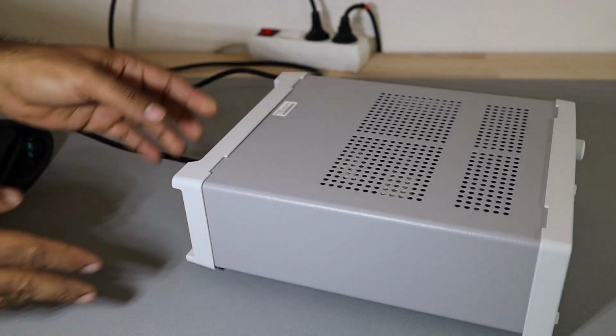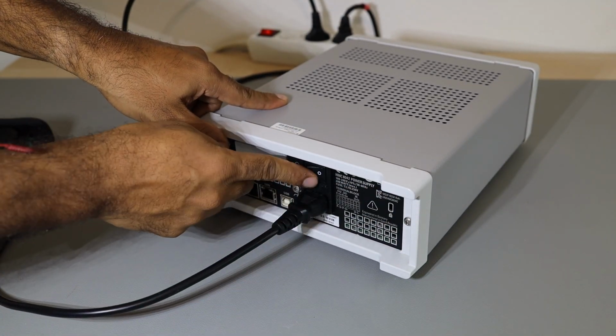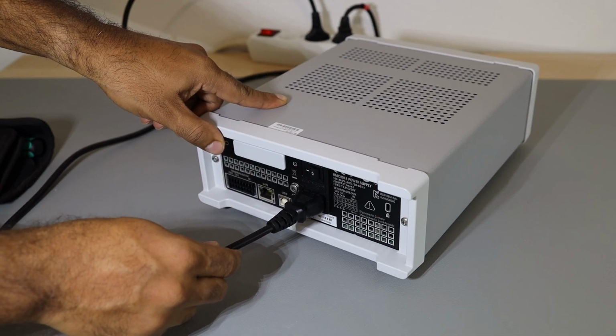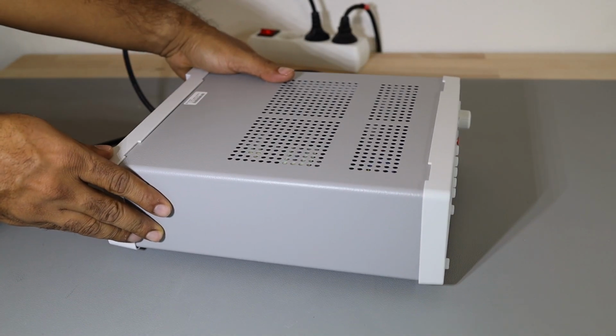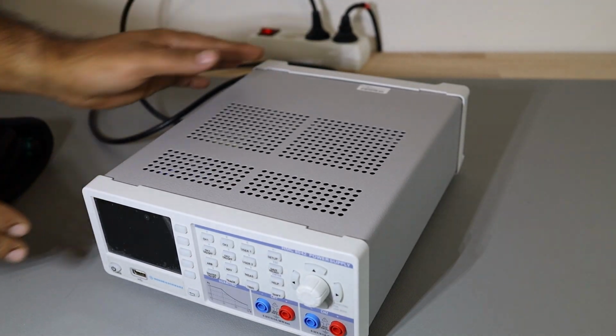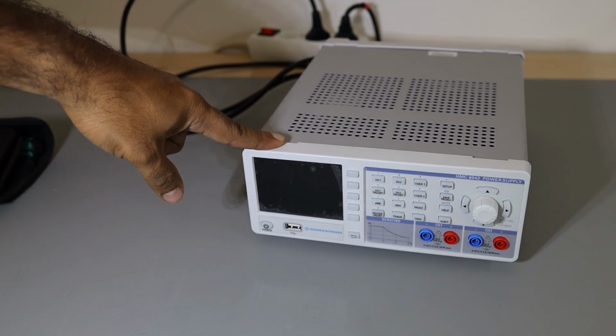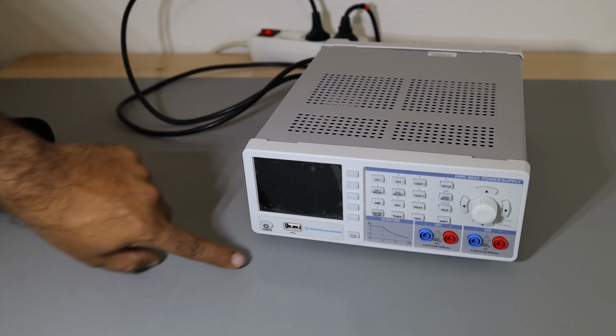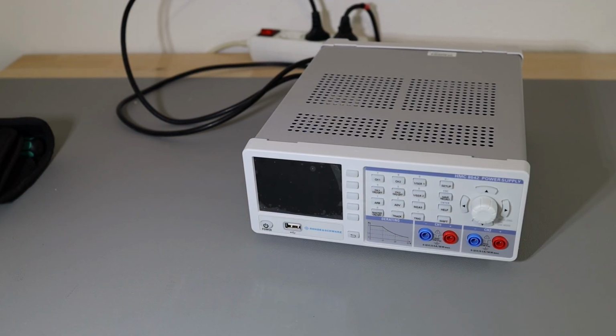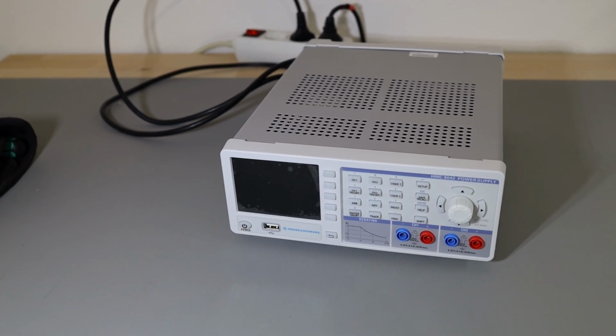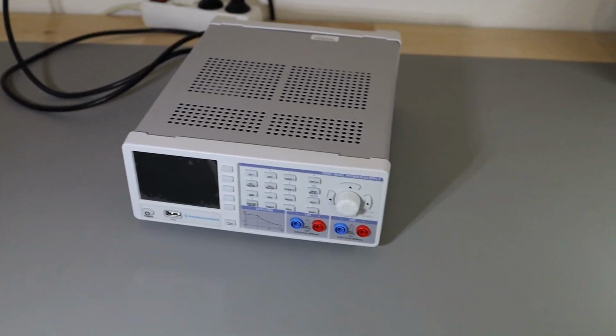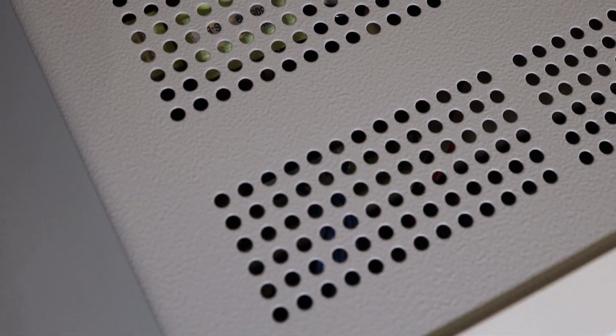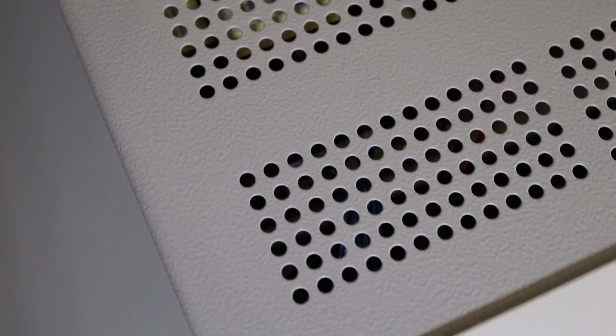So right now you can see this unit is plugged in, and I have turned on the supply as well, and on the front of the unit I do not see any power. If I press the button, nothing happens. I'll show you. The unit has received the power. The unit has an SMPS sitting on the top and it must have power. So you can see inside the SMPS, which is sitting on the top of the primary board. It is getting power, but the unit itself is not getting power.